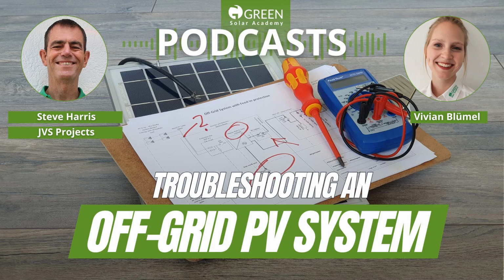Let me summarize. You already listed quite a lot of typical problems you get when troubleshooting the system. We have the customer using the system too much for the situation, wrong installation and wrong selection of components. We have insufficient design, voltage drops not considered in cable sizing, too small PV generators, or just not taking everything into account in the design process. We then have maintenance issues, not enough maintenance on the system, loose connections, dirty panels, and finally wrong preparation and wrong handling of components when commissioning them.